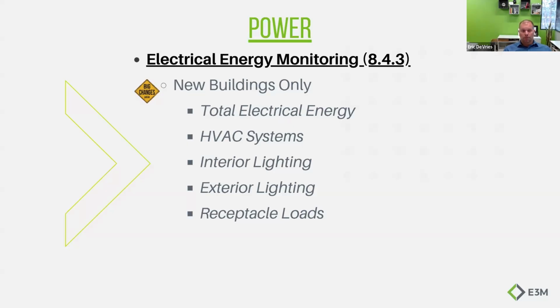This is a mess if you don't think it through from initial design. If you approach it the right way from the get-go, you might bring panels differently off your main distribution panel so you can put one meter and monitor all your HVAC from one panel. If you just start distributing power everywhere, you get a real mess trying to figure out lighting load versus HVAC load versus plug load if one panel serves the entirety of an office.